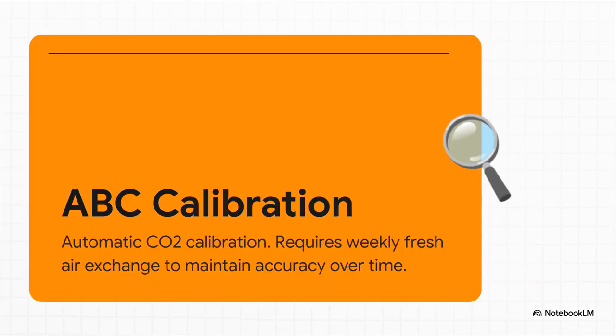The sensor has also got some brains built right in to cut down on maintenance. The CO2 sensor features something called automatic background calibration, or ABC. Basically, if the room it's in is guaranteed to get fresh air at least once a week, the sensor uses that low point as a baseline to automatically correct itself for any long-term drift. It keeps itself accurate over time, all by itself.